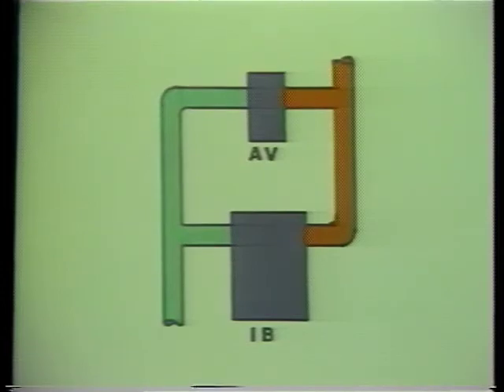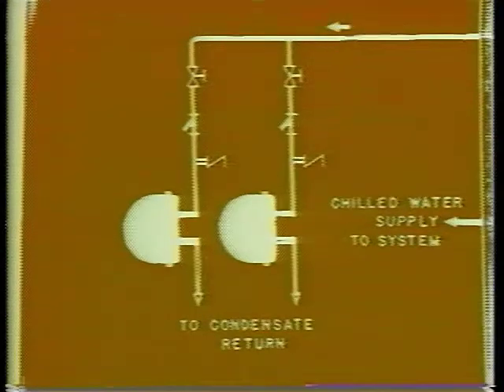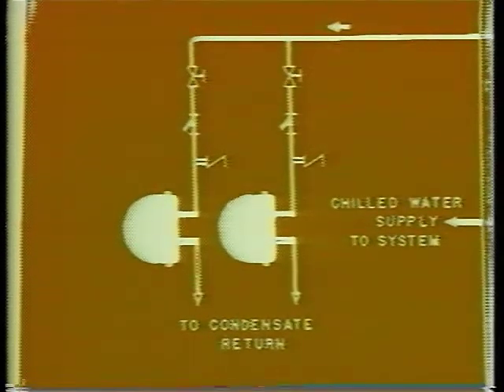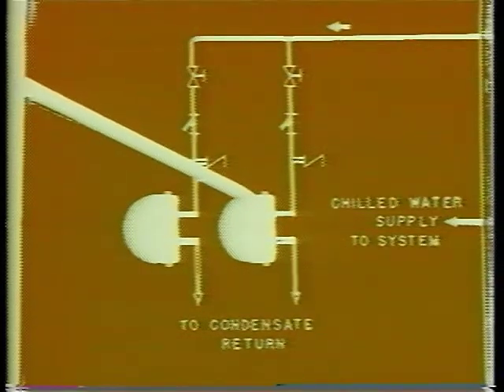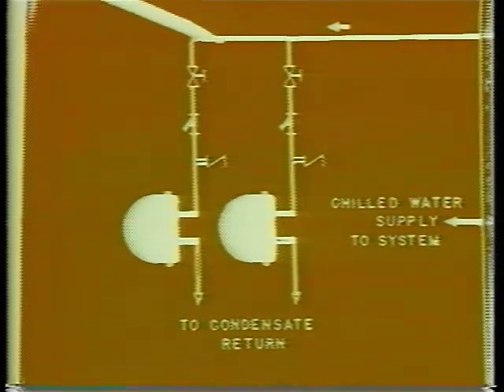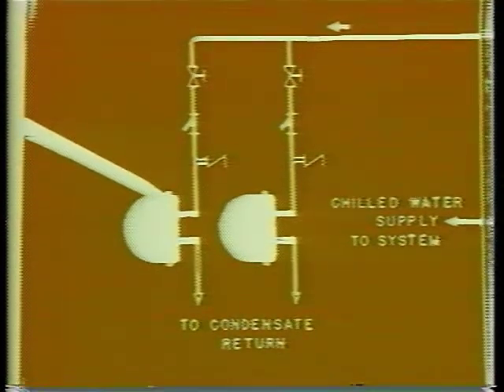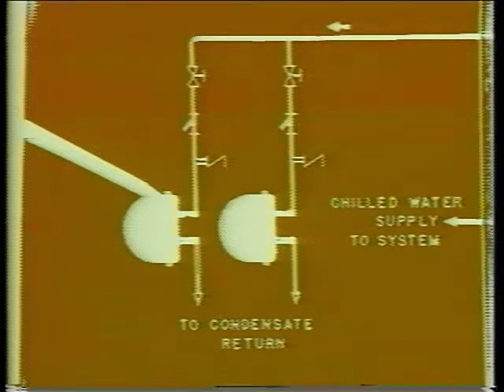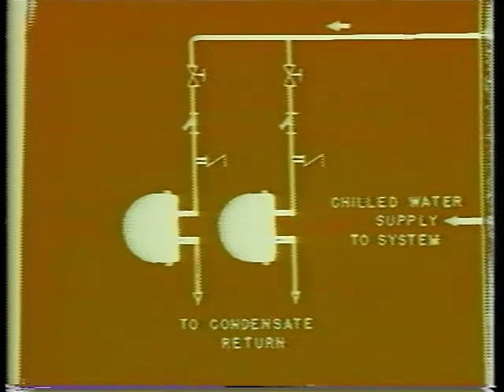As the cooling load on the chiller increases, the steam pressure rises. Then, the thermostatic air vent in the F&T will vent the air which entered the steam space through the vacuum breaker. Thus, the chiller quickly responds to the increased cooling load. An inverted bucket trap with an external thermostatic air vent would also be acceptable for draining the steam absorption chiller. Regardless of the trap used, a standby trapping system is recommended for this service. Should a component in the drainage system need maintenance, the chiller can operate on the standby system while the repairs are being made. The standby trap ensures continuous, uninterrupted service.